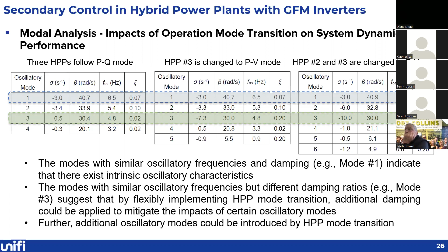With the operation mode transition, we can identify some unchanged oscillatory modes, representing the intrinsic oscillatory characteristics, particularly the couplings between different units, for example coupled through the main power circuits and the power network. We also identify that when we trigger some operation mode transition, some oscillatory modes may have increased damping ratio, which is beneficial for dampening small signal instabilities. But we also need to highlight that there might be some additional oscillatory modes triggered as well—something we need to avoid when coordinating the selected operation modes across the overall HPP.